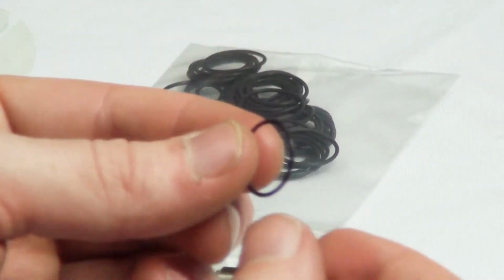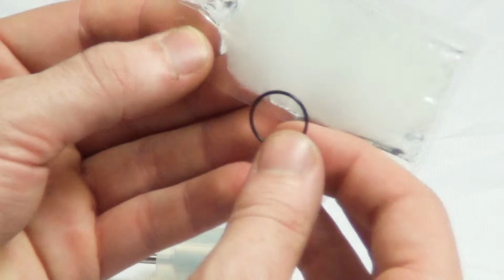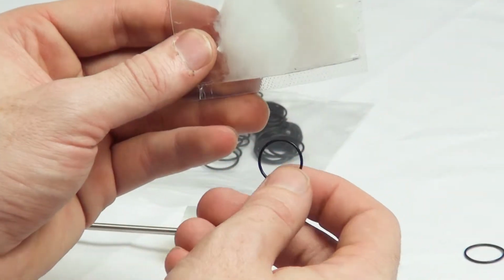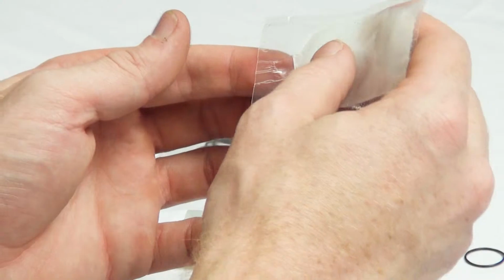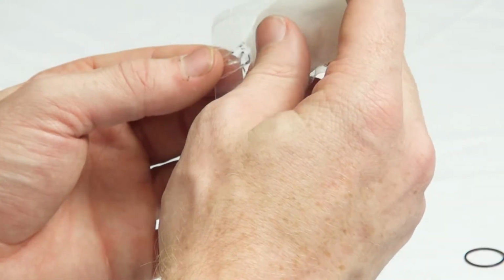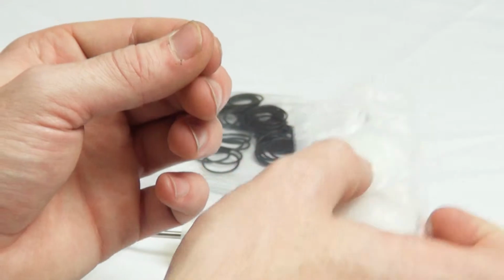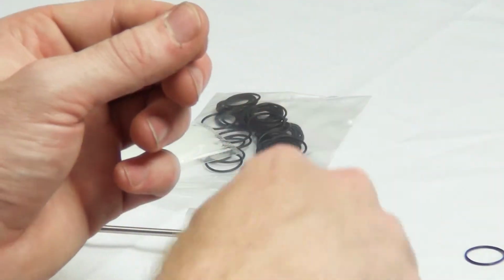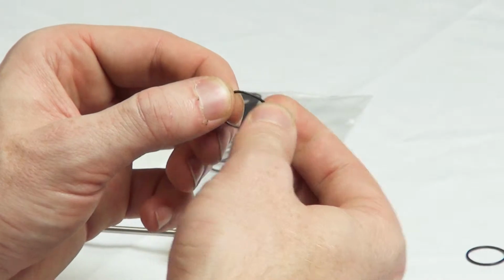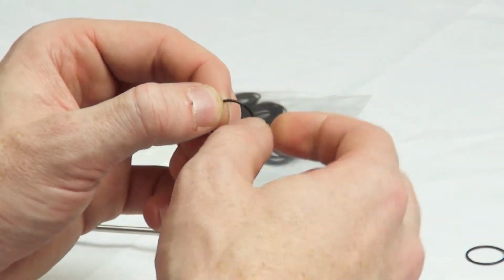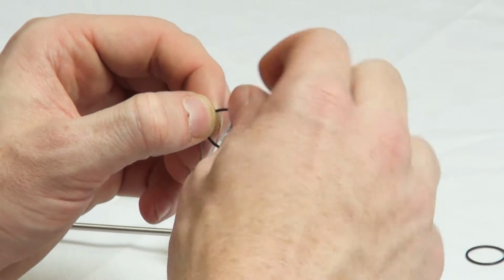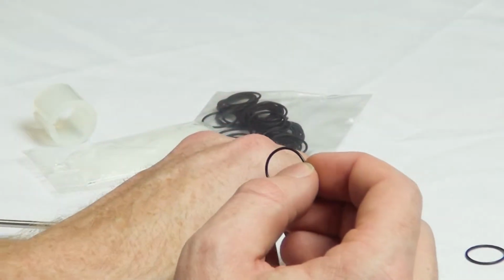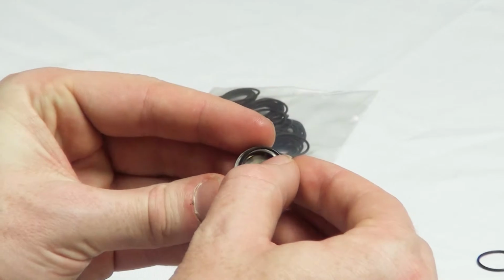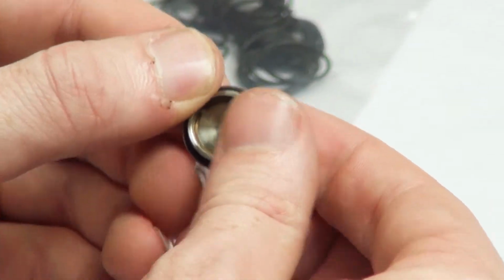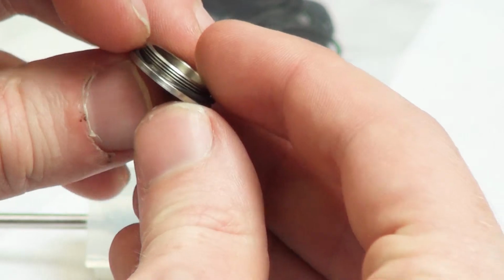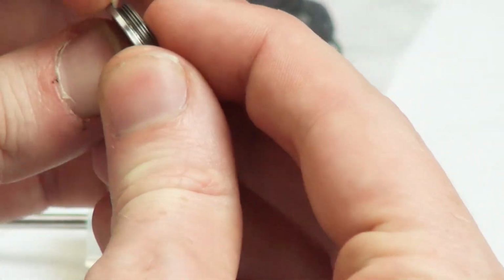Next, apply silicone grease to the new O-ring. Do this by rubbing a small amount on your index finger and thumb, and then slowly pulling the O-ring through your fingers to fully coat it. Then place the O-ring in the groove of the battery cap. You can use your fingernails to make sure it's fully seated.